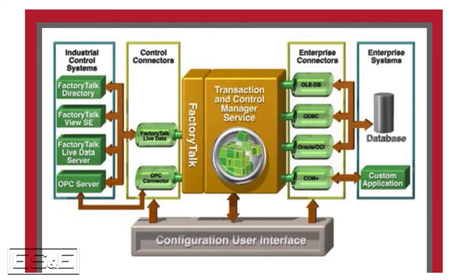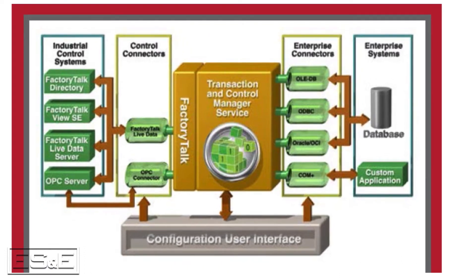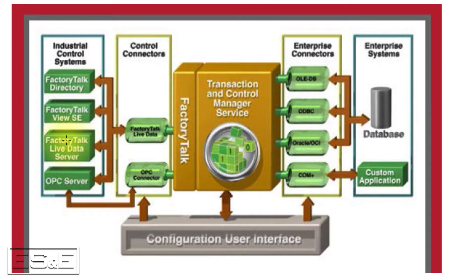Transaction Manager can pull data from Rockwell sources. Because it is a Rockwell product, it has a native interface into FactoryTalk LiveData, which means it can connect to FactoryTalk Directory, FactoryTalk View SE, the FactoryTalk LiveData server, and any OPC servers that are defined within that FactoryTalk application.